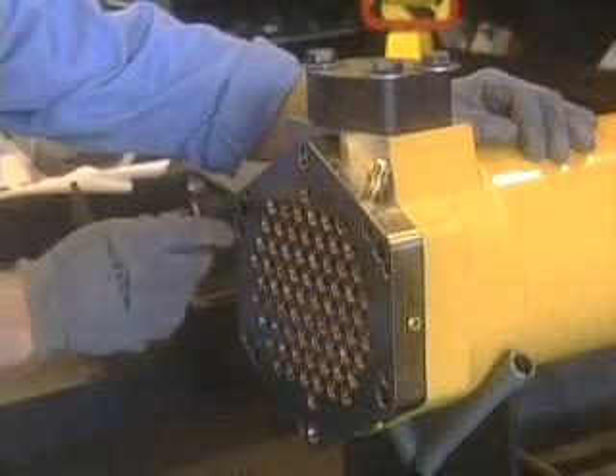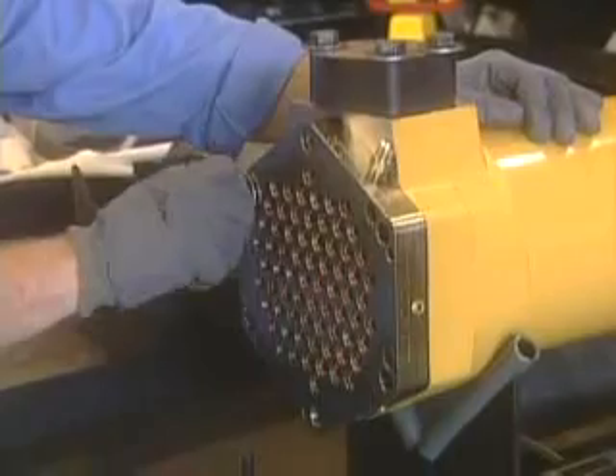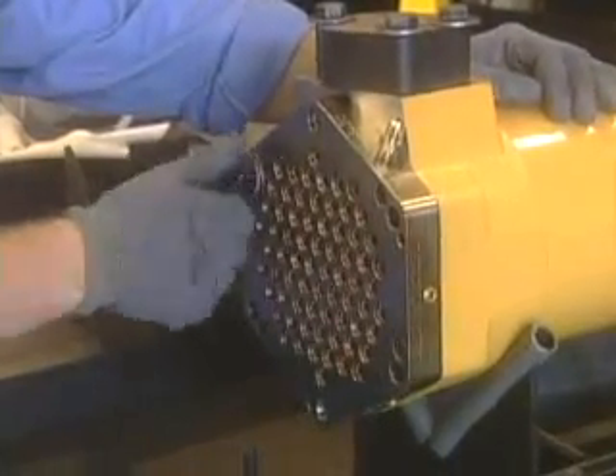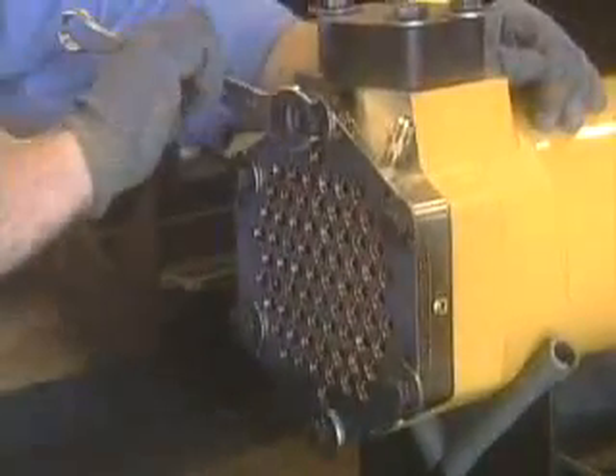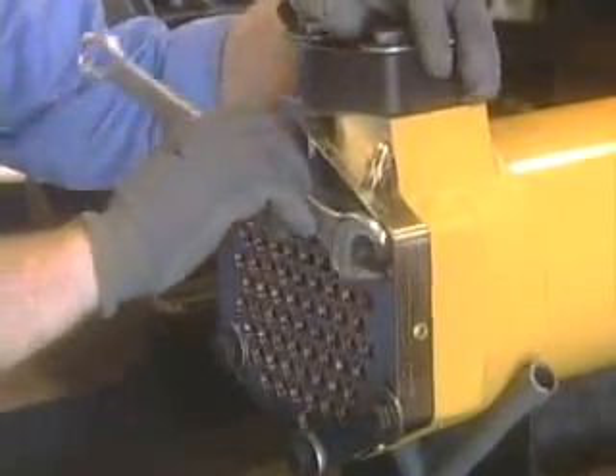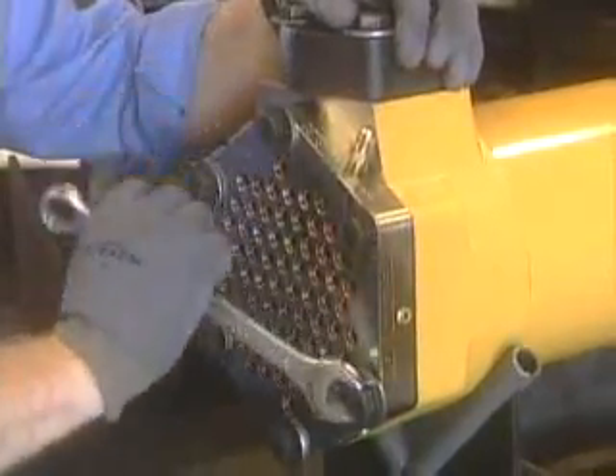Start by installing shell side test plates. Install an appropriate length bolt and flat washer in all flange locations on both header plates to provide header to frame clamping. Then tighten. With the cooler under water and after residual bubbles are gone, begin the test sequence.